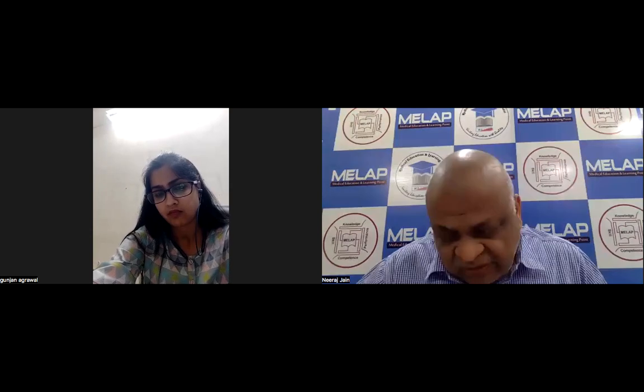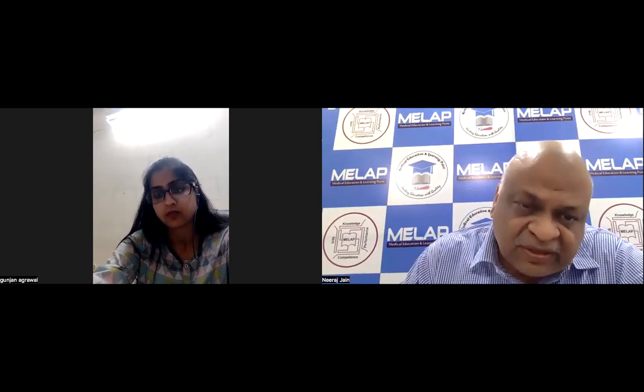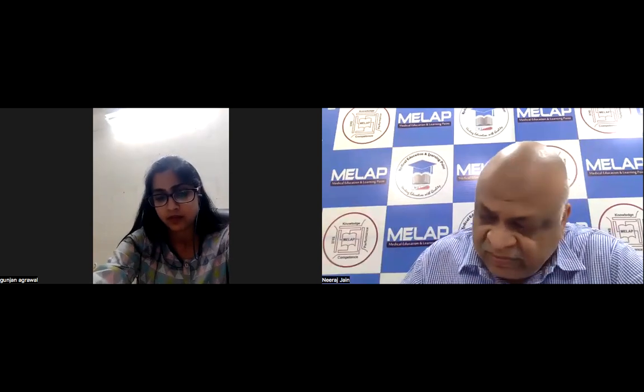So you conduct a meeting. In that meeting you decide: the manufacturer is recommending a variation of 2, and in our laboratory we are getting a very high degree of precision. Following that precision is not clinically relevant. So in our laboratory, we will follow the mean, whatever we are getting, that hardly makes any difference. And for standard deviation, somewhere in between, you can set it based on your documented clinical meeting, which is definitely not more than the manufacturer's standard. Okay, sir.